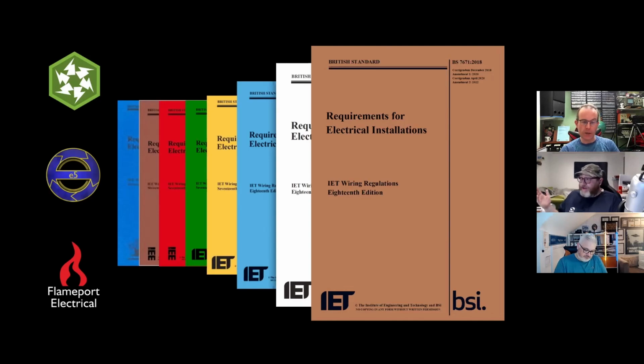We may have EIC forms in 10 years that say source of supply TNCS/TT with an island mode effect. That won't happen - we'll always pick the worst, it won't be TNS, because there is no TNS anymore. You'd have to consider both if you're going to have those two sources of supply.